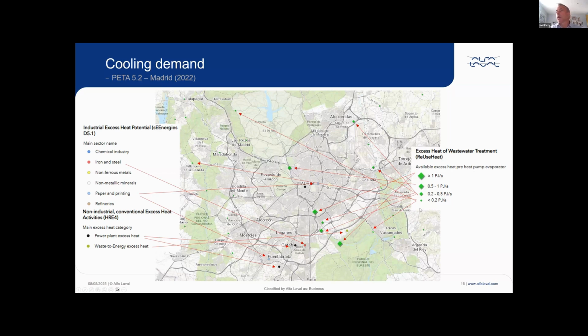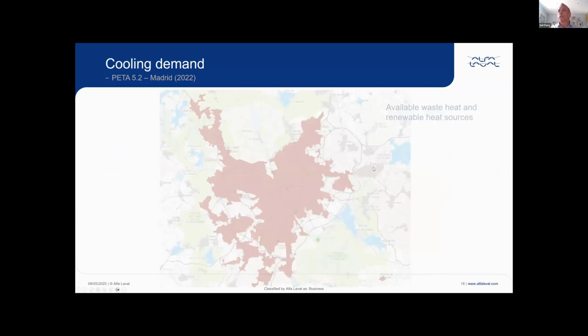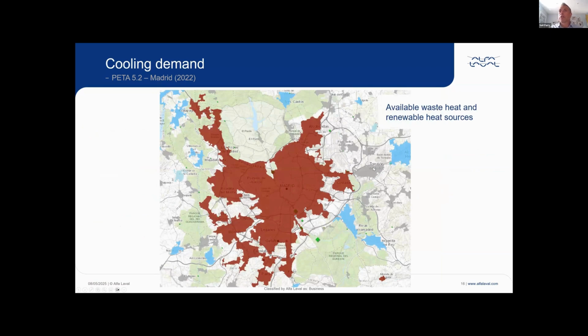And then we look on the sewage or the wastewater side, we can see there are significant wastewater options as well, where there's waste heat. And again, to repeat, that wasted heat can be turned into cooling. That's the important aspect, really. And when we overlay that graphic with the available renewable energy and waste energy, we see that we can actually cover the vast majority of Madrid's requirements just from the waste energy that we currently are wasting. And that is not a 2050 slide. That is as of 2022. So significant opportunities there to provide cooling from the waste heat that we already have.